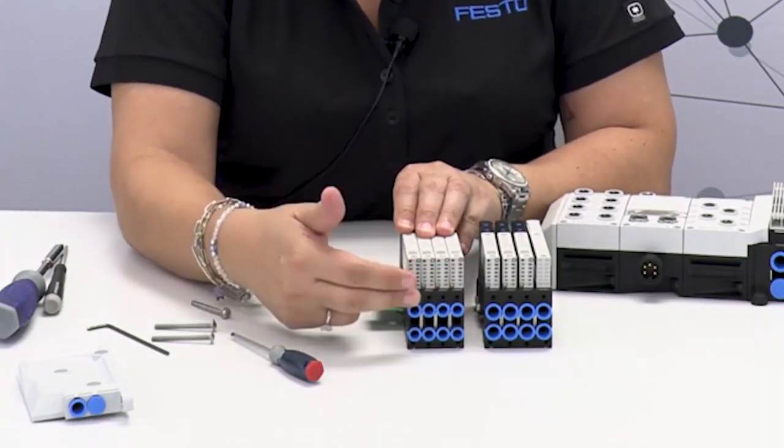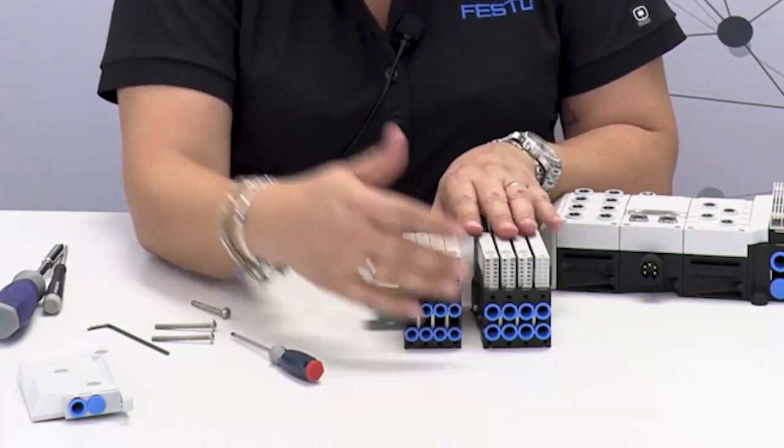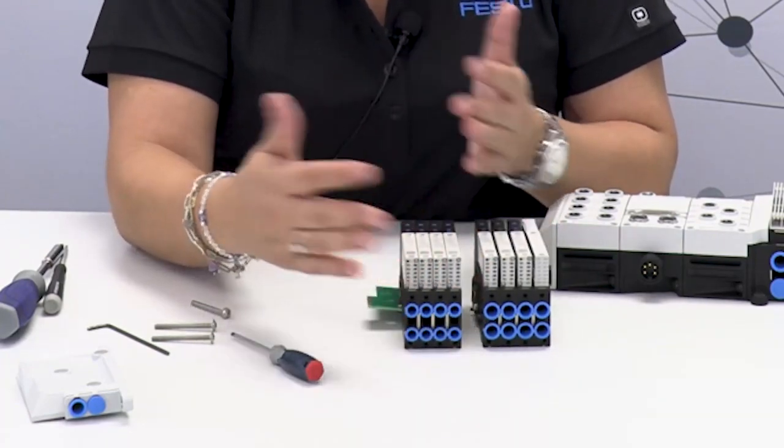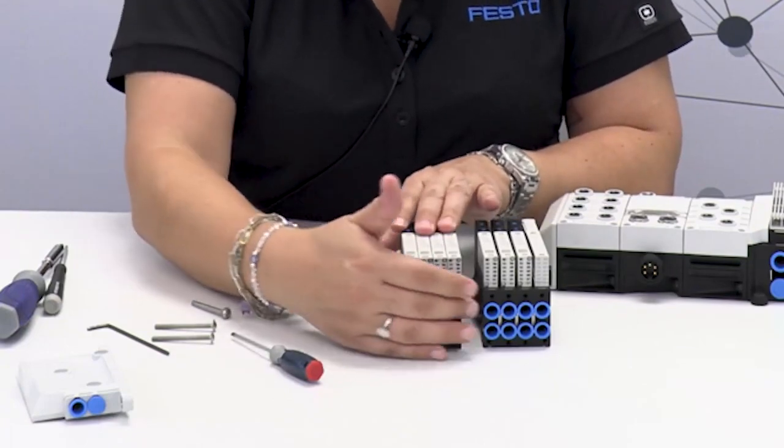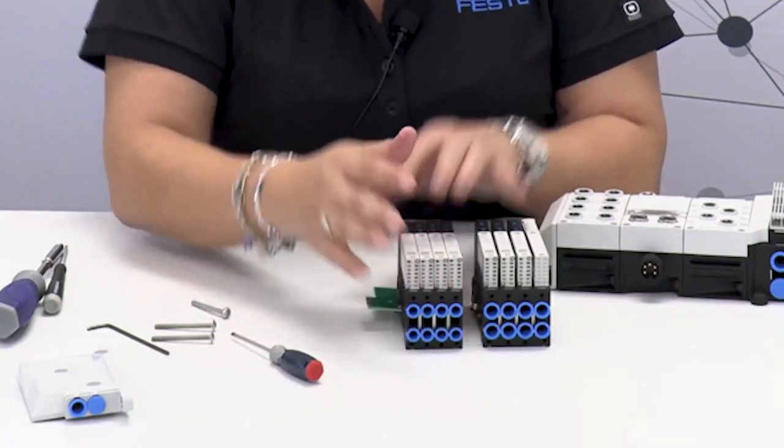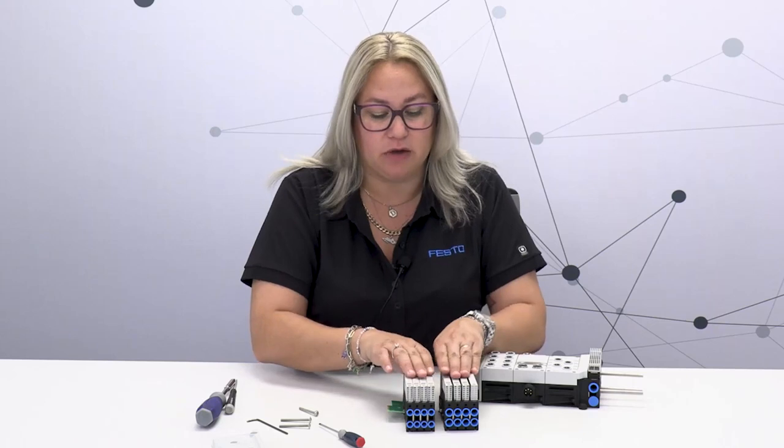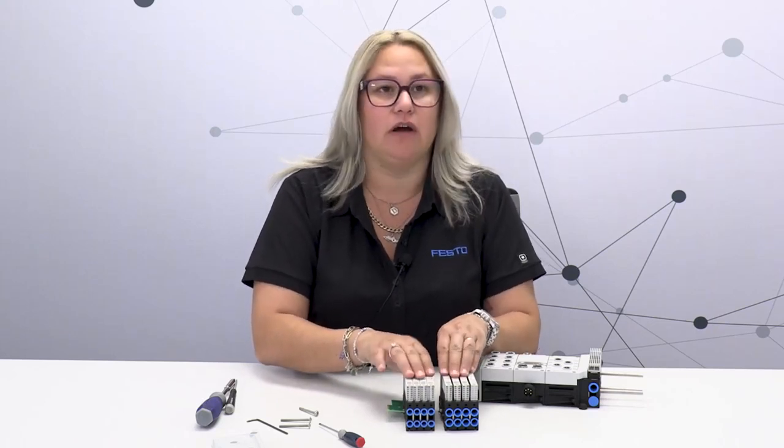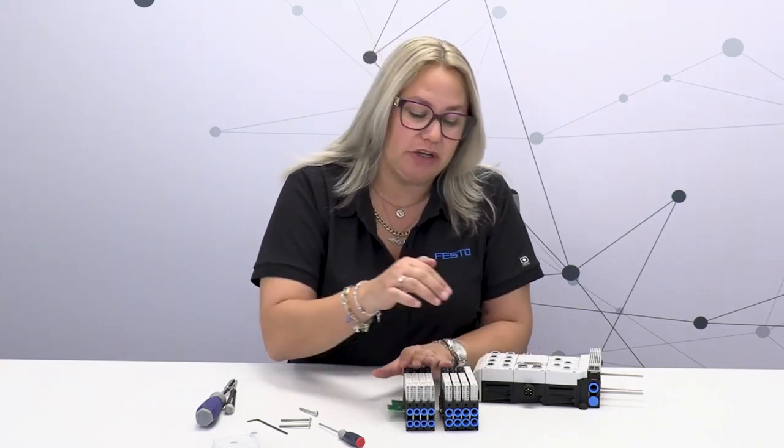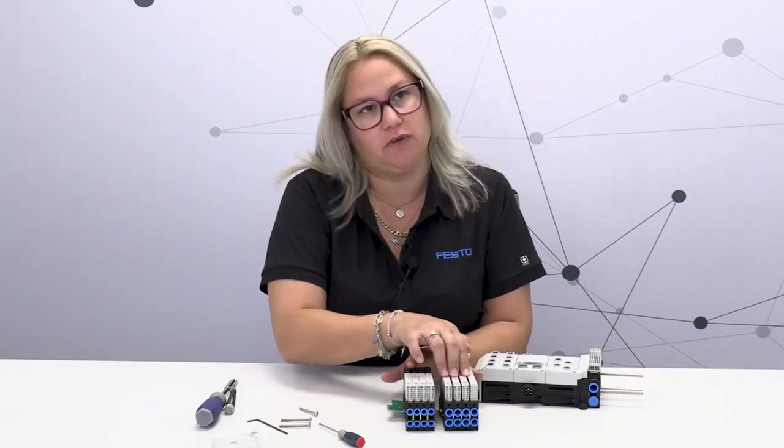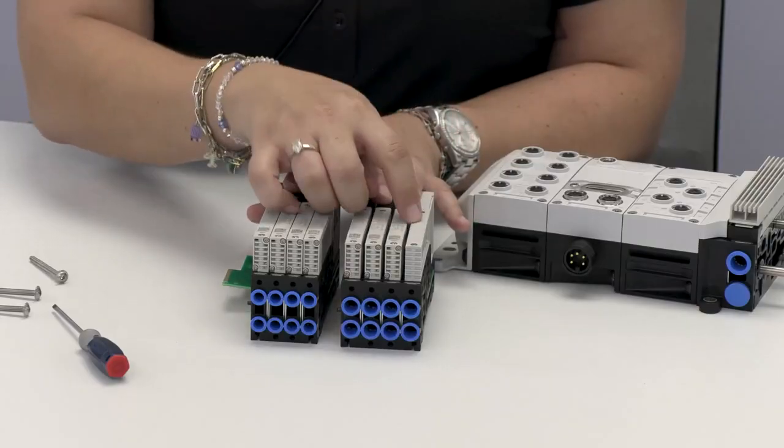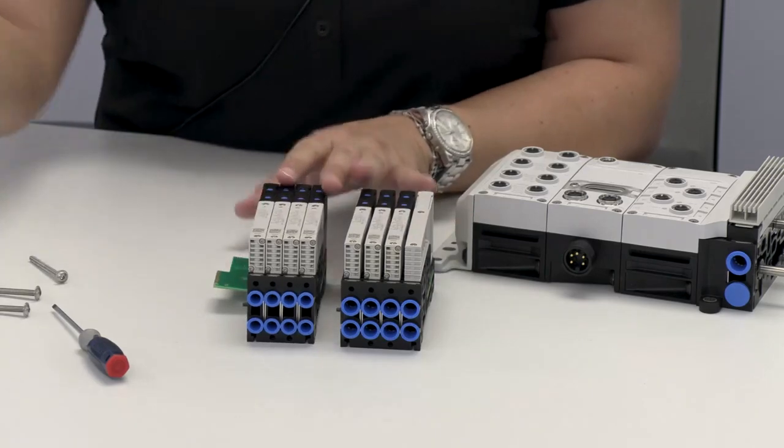We have options of six millimeters or one quarter, one eighth, eight millimeters, five sixteenths, all the different options and it's just a matter of changing the sub base. This really allows for a lot of optimization in the machine. You can have some smaller valves with larger flows. This valve can flow up to 670 liters per minute.